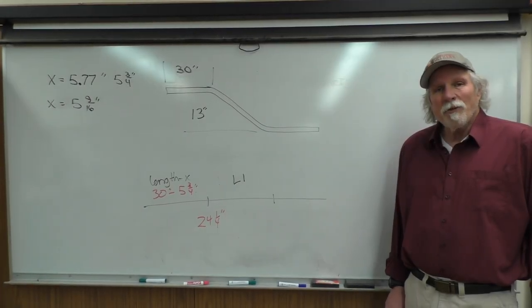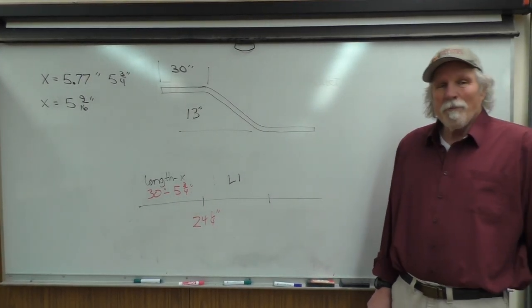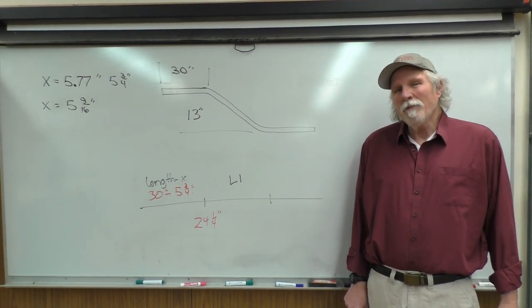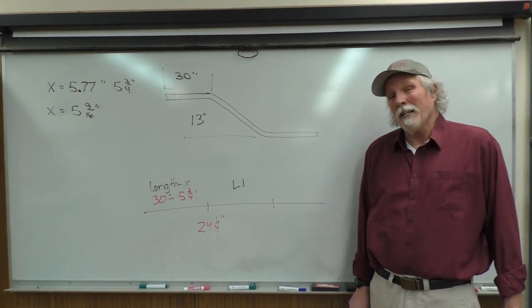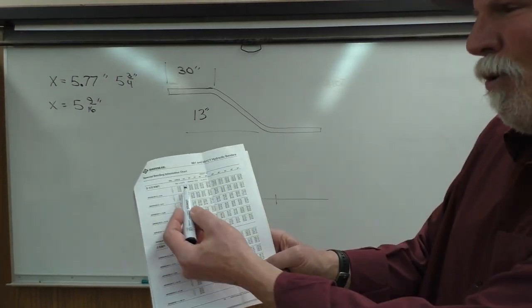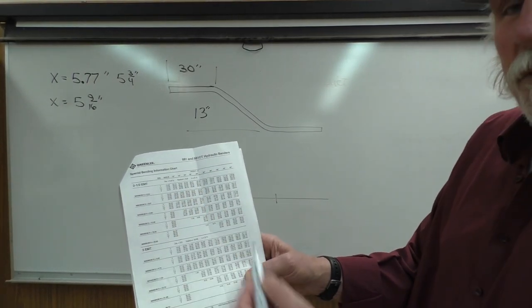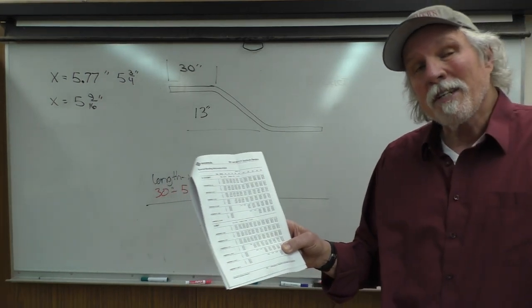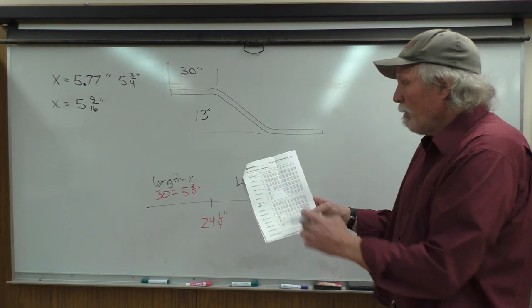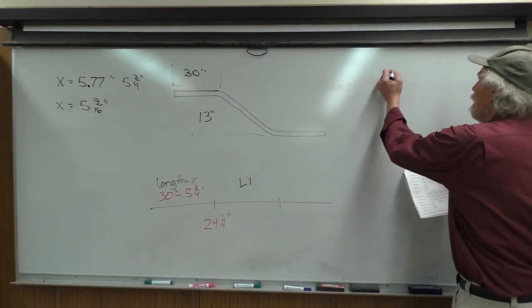Okay, so we were bending 3-inch EMT conduit with the hydraulic bender. And when we bent the last one, we had a 15-inch offset. But what do we do if we've got a 13-inch offset? Well, the manual has values for 10 inches, 12 inches, 15 inches, 18 inches, 24 inches for the offsets. Well, we need to figure out what the value would be for 13.